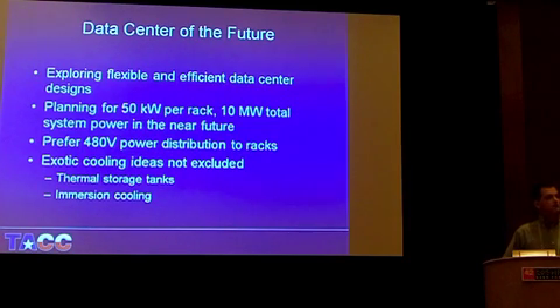We've been encouraging vendors to do more 480 volt power distribution to the racks, to really improve the efficiency of power delivery. With the PDUs spread throughout the room, new technology now allows in-row PDUs, which we're exploring so we can get power as close to the compute racks as possible before stepping it down.